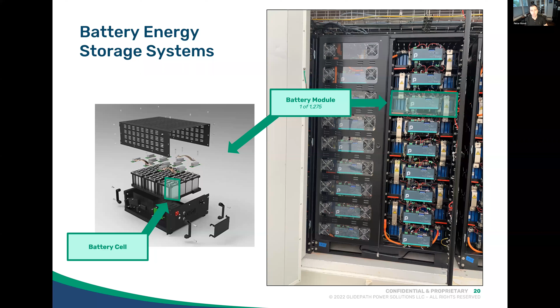These operate similar to how data centers work, with a cold column and a hot column, though each project is designed a bit differently. In this project in Texas, the cold column is in the middle. You can see in this picture an orange bag-like curtain at the top of the container, hooked to the top. That curtain runs from the HVAC unit on the end and hangs down partway into the containers, behind the racks, dropping cool air in. The fans pull it across and through the battery modules, and out. The door side is the hot side.